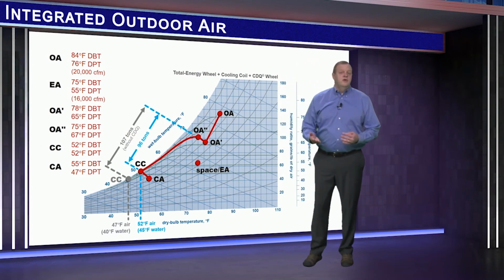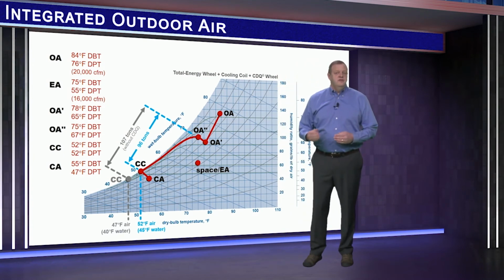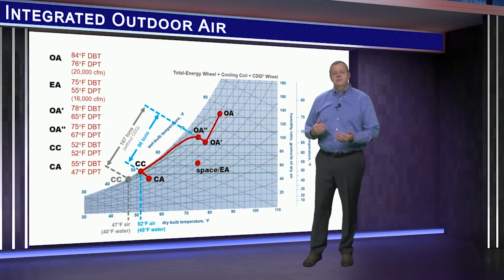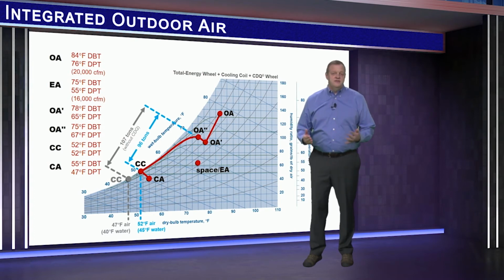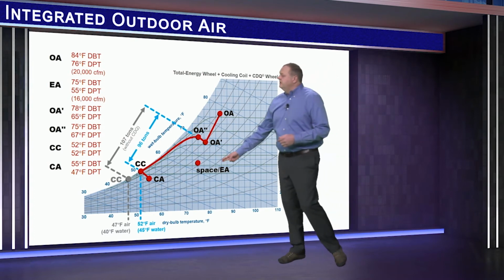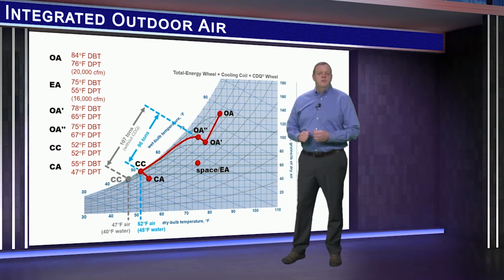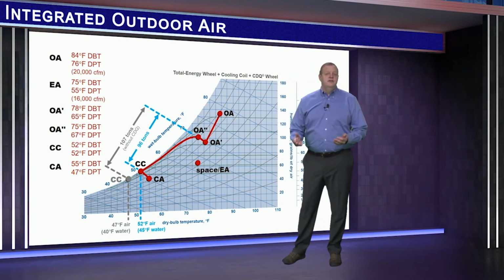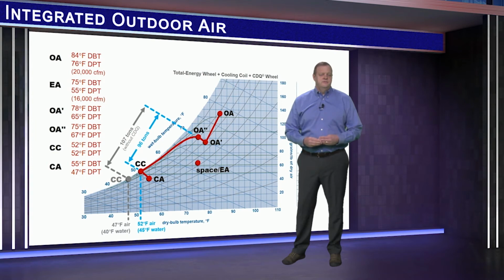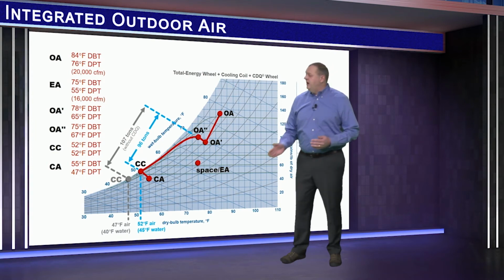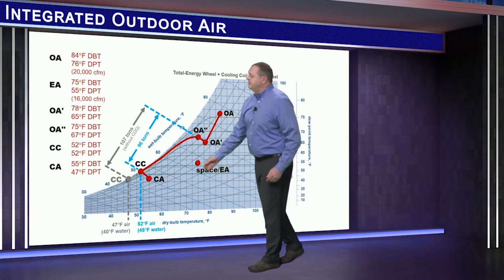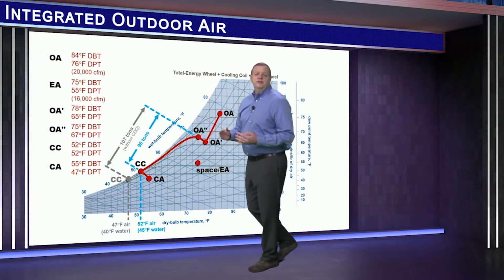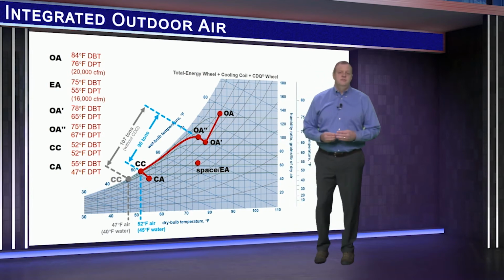And because the cooling coil only needs to make 52-degree air, the chill water supplied to it may not need to be as cold. In our example, we're using only 45-degree water compared to 40 degrees in the configurations without CDQ. Now, this process of adsorption does release a little bit of sensible heat, and so the air leaves the unit at 55-degree dry bulb and 47-degree dew point.